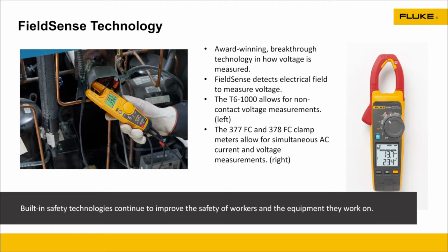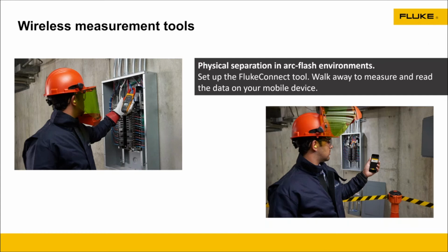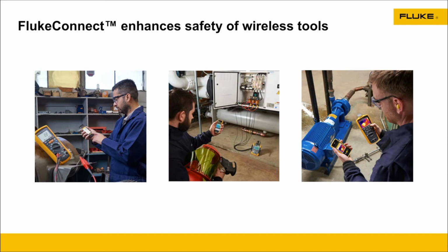The T6, the 377 and 378 allow you to make that non-contact voltage measurement without using your test leads. Again, a safer way of doing your job. Also key is trying to stay out of that arc flash zone. There are now tools that have Bluetooth built into them, or even Wi-Fi. Fluke Connect is a Bluetooth capability. Any meter that says FC on it, we can put that meter in, step away and use a smart device, an iPhone or an Android phone, and see the measurement on the phone itself. Again, we've energized the line, and we're staying out of that arc boundary of potential energy. And with some of these, as you can see in these pictures, there are multiple different ways of making those measurements and working with those tools.